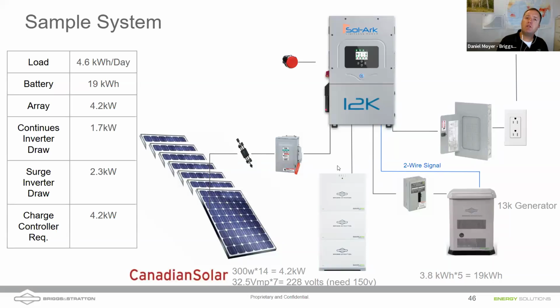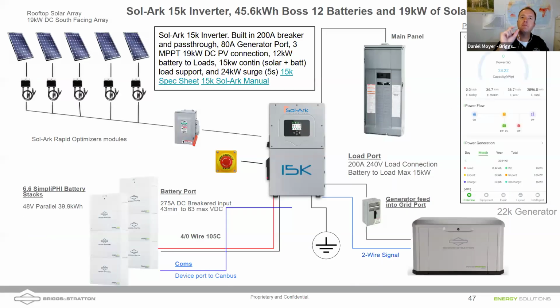One thing I want to mention is we need to run the panels in series to build up the voltage, making sure we're operating within the parameters of our charge controllers. On the Sol-Ark 12K, we need at least 150 volts DC on the solar photovoltaic side, and we can't exceed about 425 volts. So I'm going to have 2 strings of 7 panels, bringing us up to 228 volts. That's perfect, operating right in the middle of the charge controller's operating window. Let's step it up.